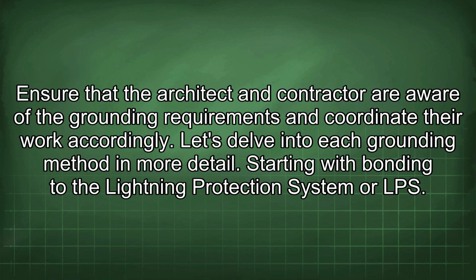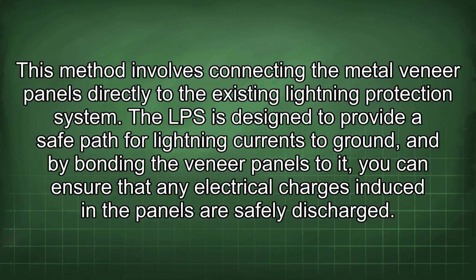Let's delve into each grounding method in more detail. Starting with bonding to the lightning protection system, or LPS. This method involves connecting the metal veneer panels directly to the existing lightning protection system. The LPS is designed to provide a safe path for lightning currents to ground, and by bonding the veneer panels to it, you can ensure that any electrical charges induced in the panels are safely discharged.